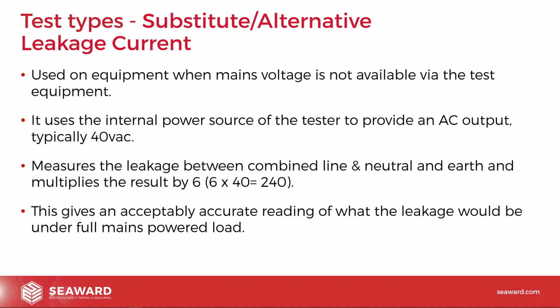The final one to talk about is the substitute or alternative leakage test. When we're doing this test, it simulates what you would do if you were doing a normal leakage test. So if you've got purely battery powered equipment, you can't put mains into the tester. You can't add 230 volts, 240 volts to equipment. And maybe you don't want to power equipment up because it would be dangerous and you can't do it in that environment or whatever.